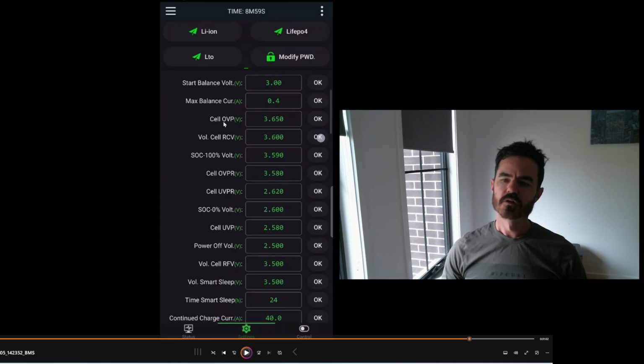So for the cell over voltage protection, that's set at 3.65 volts, which is okay, happy with that. The state of charge is 0 to 100%, meaning once any of the cells hit 3.59 volts, the state of charge will reset to 100%.